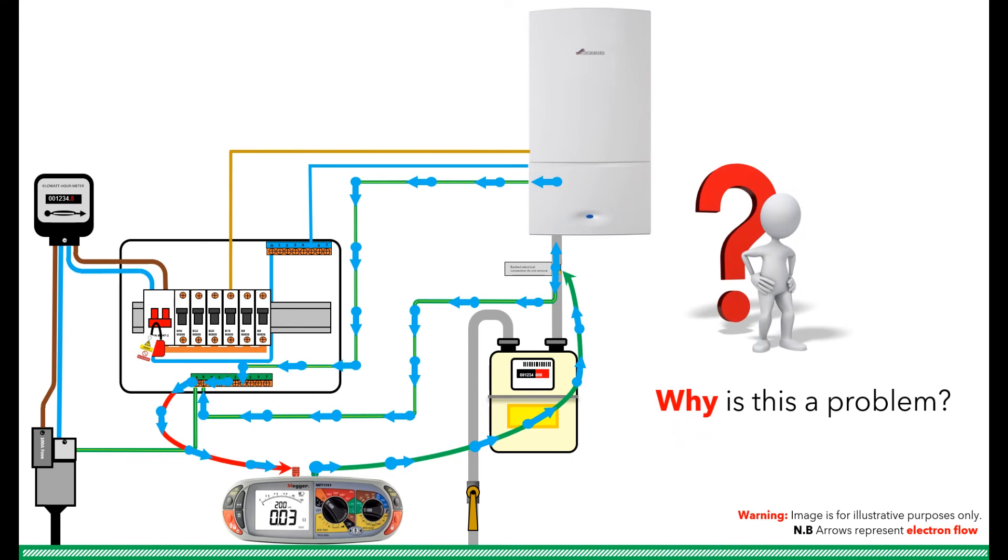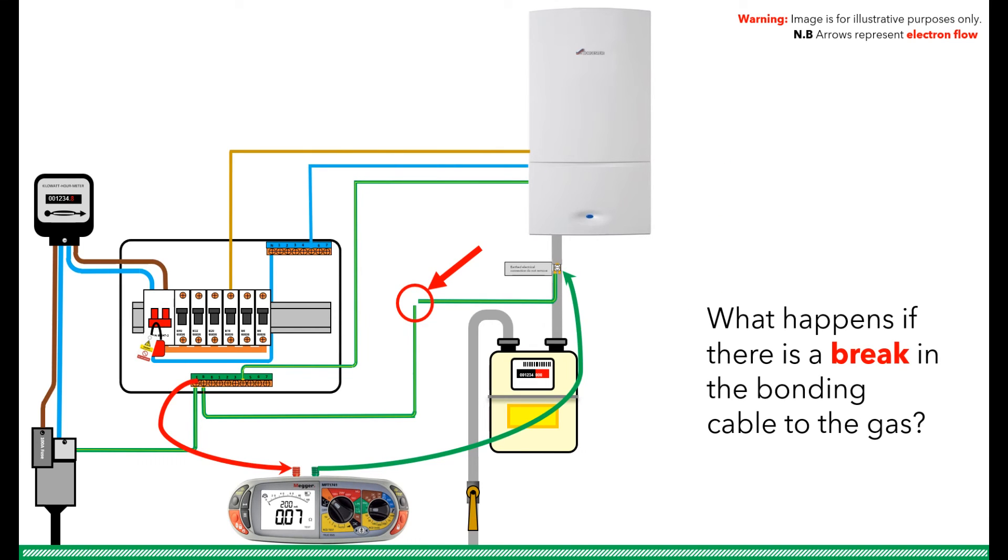So why is that a problem? Because surely that means the resistance is lower, and that is a good thing. After all, we were told the lower the resistance in a healthy circuit, the better. Well that is true, but what happens if there is a break in the main bonding conductor and we no longer have continuity? Our low ohm resistance tester will display a resistance reading as the circuit is still completed through the CPC, but it means we potentially no longer have the protection to the extraneous metal gas pipe that we discussed in the first part of this video.